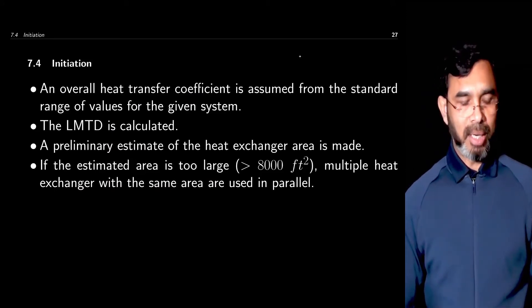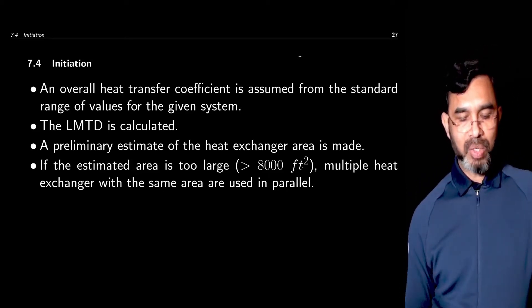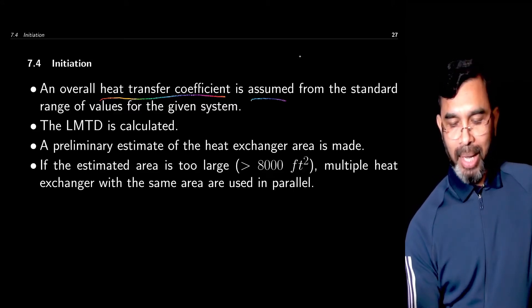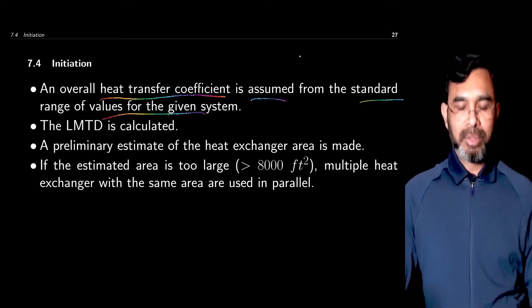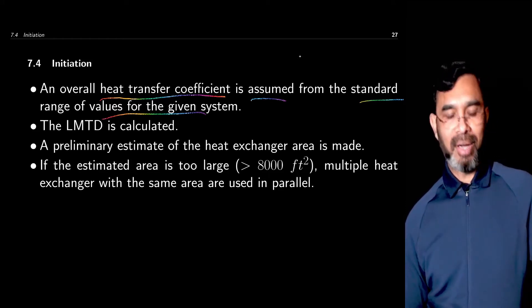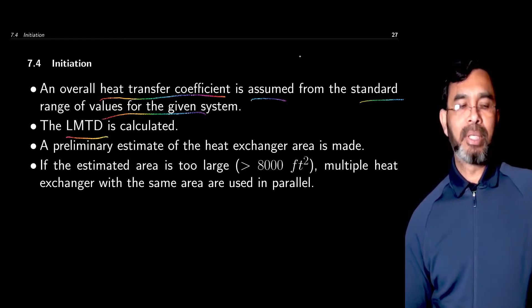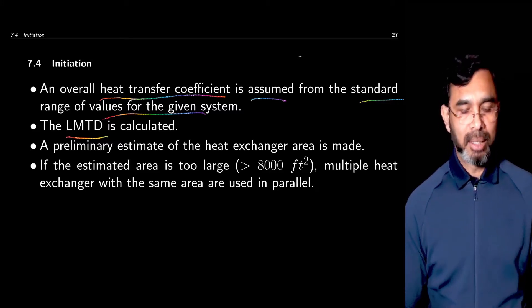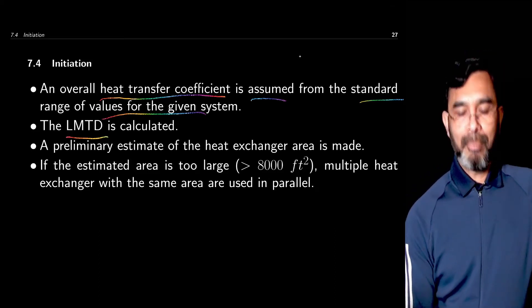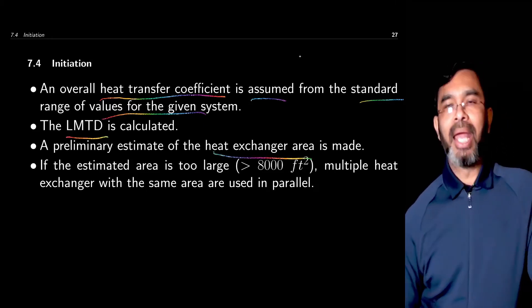Once the fluid allocation is done, the initial energy balance is complete, and you have confirmed there is no temperature crossover, the design procedure starts with the assumption of an initial heat transfer coefficient. This is done from standard range of values for the given system and fluid pair. We start with some assumed value within the given range and then calculate the log mean temperature difference. For a shell and tube heat exchanger, the log mean temperature difference is used. When you have the overall heat transfer coefficient assumed and the log mean temperature difference estimated, a preliminary estimate of the heat transfer area is made.